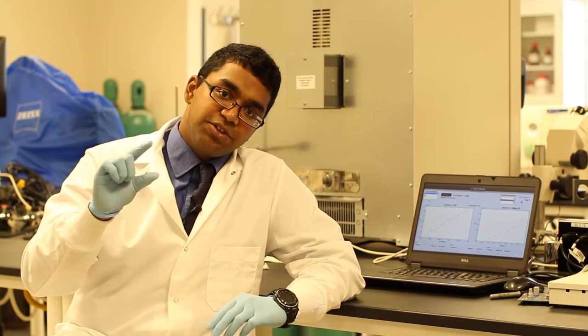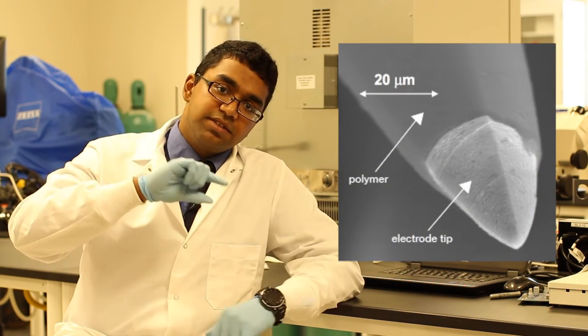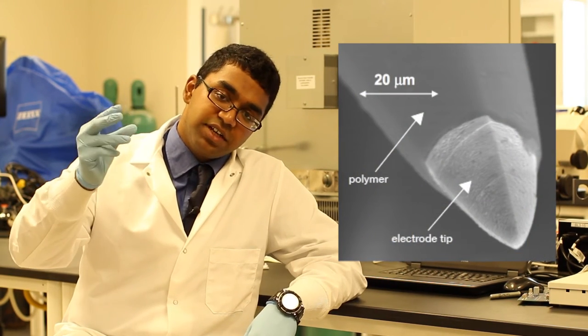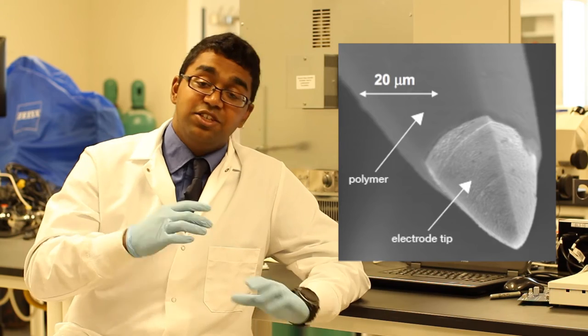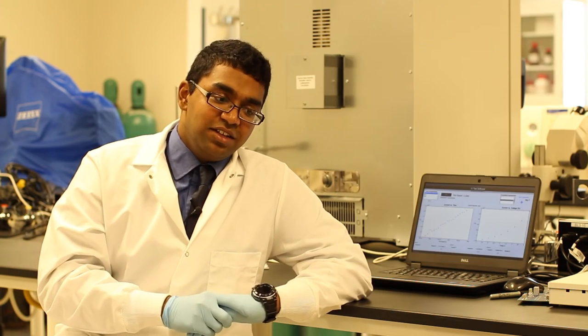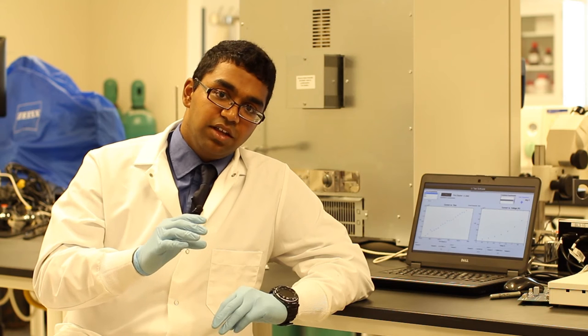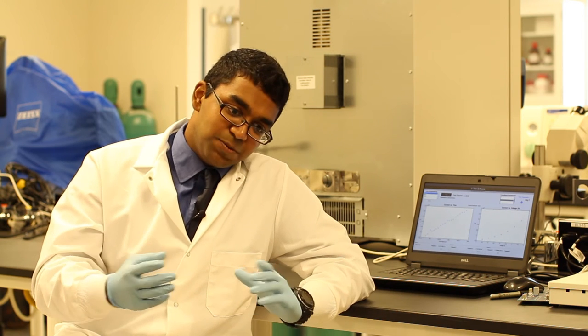Only that part of an electrode that we have is exposed to the cell that we need it to be. It needs to be totally insulated. To test the reliability of this insulation, we need to run these leakage current experiments.